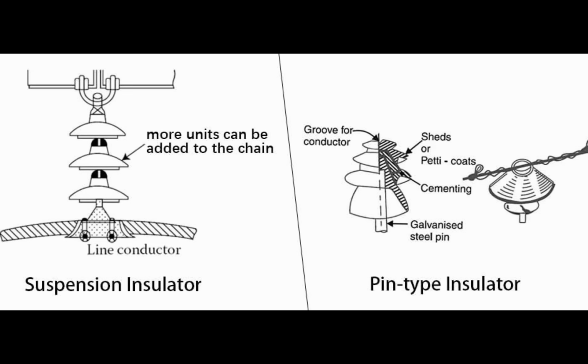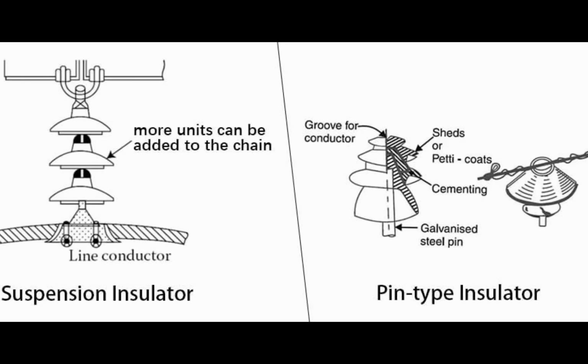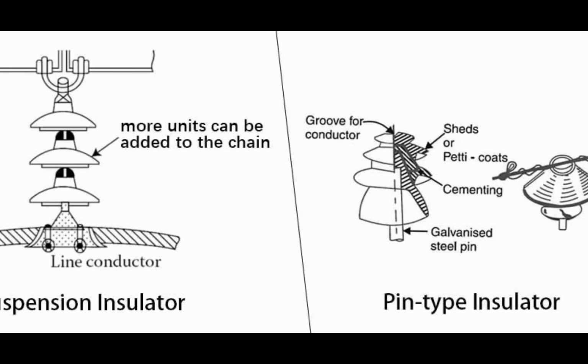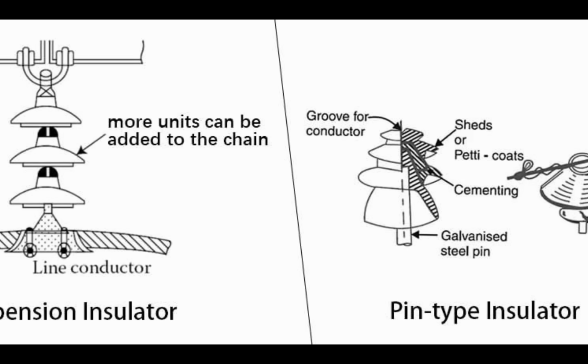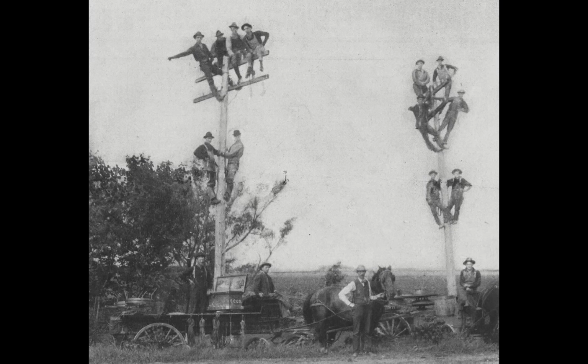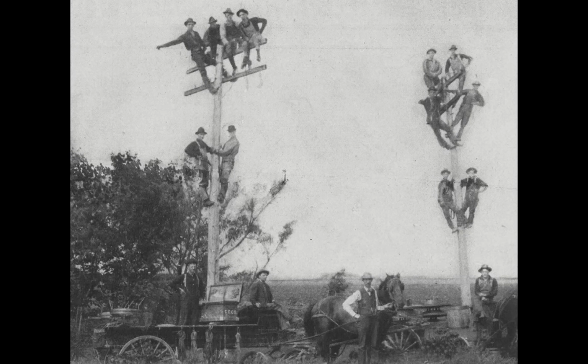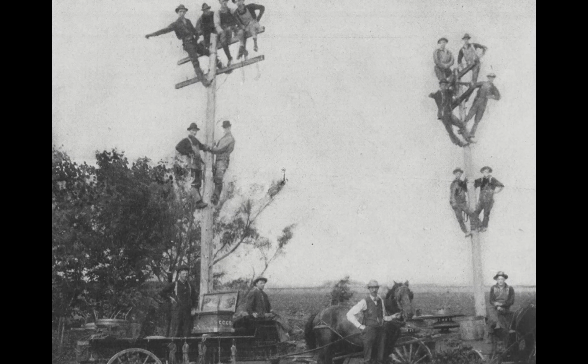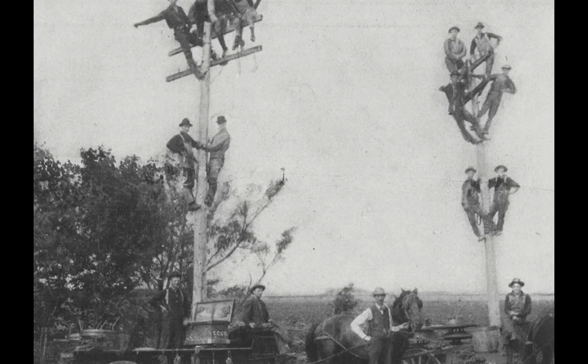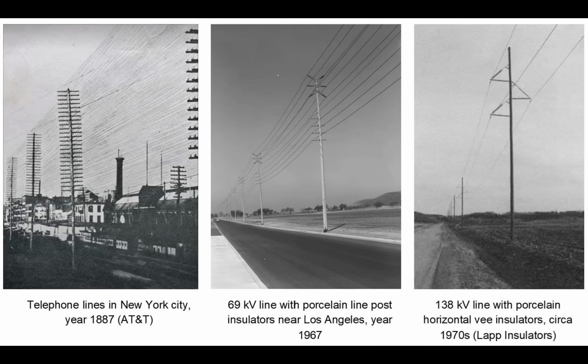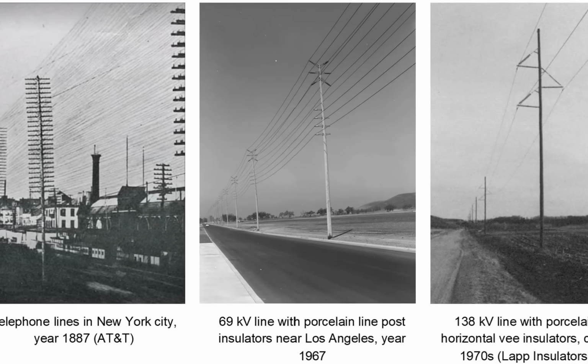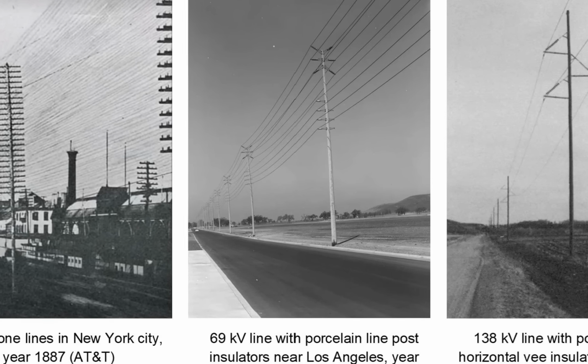Each disc was relatively small and cheap to manufacture, similar in basic shape to a porcelain plate. A metal cap was cemented to the top of each disc, and a metal pin was cemented to the bottom of the disc above it. These caps and pins interlocked, so discs could be strung together. One disc for low-voltage applications, 6 discs for 66,000 volts, more discs for higher voltages still, into what engineers called an insulator string.